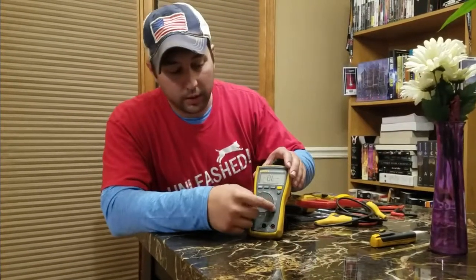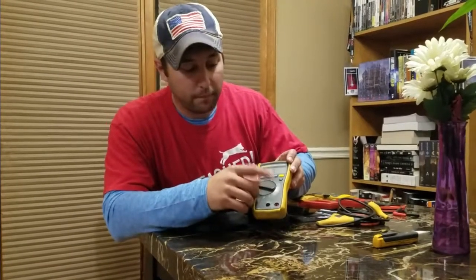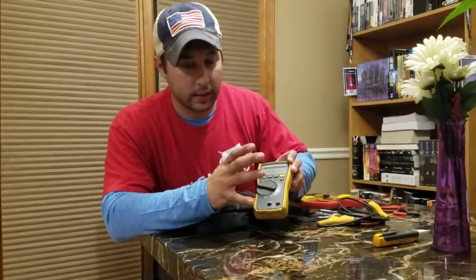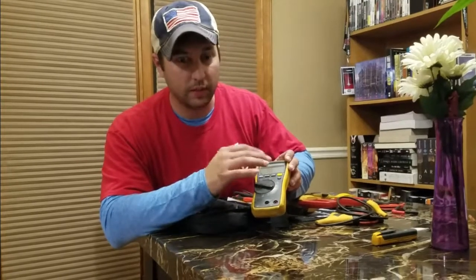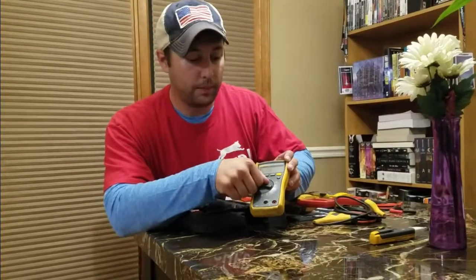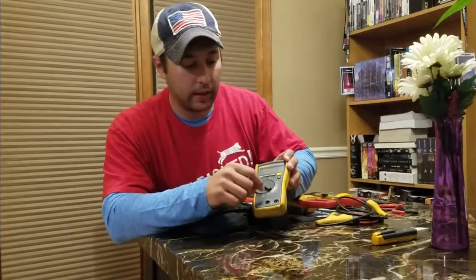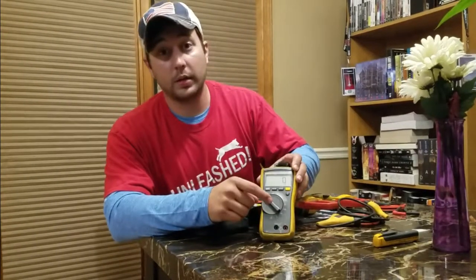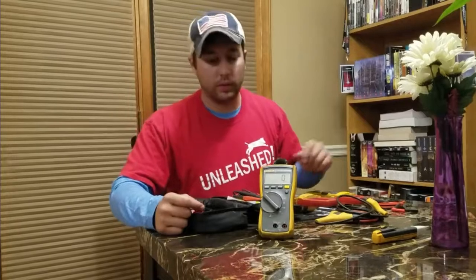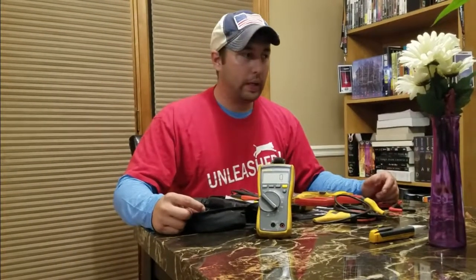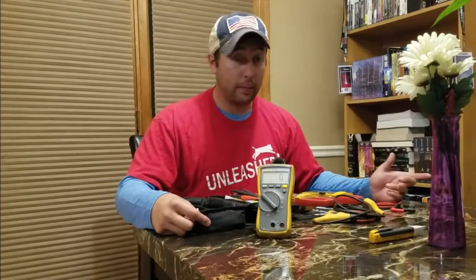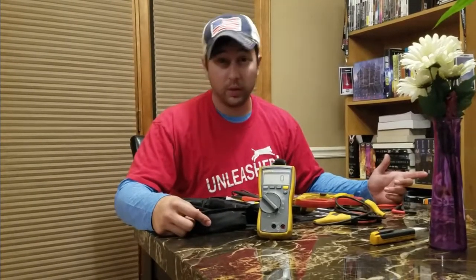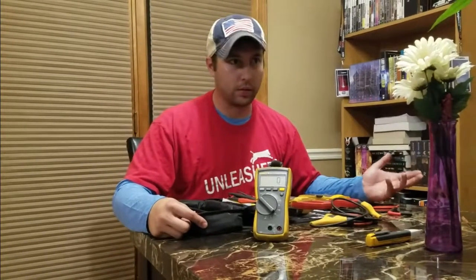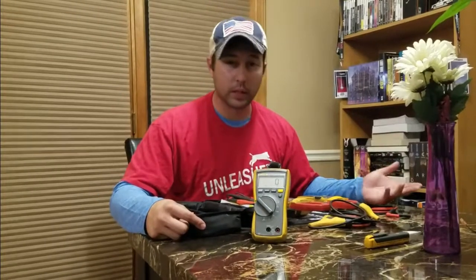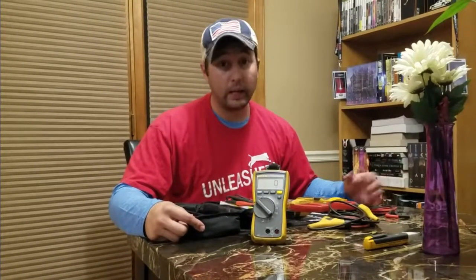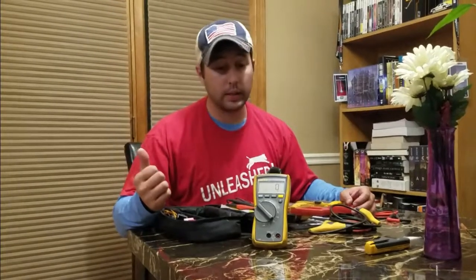The next feature down is continuity, which is the test light feature again, just without giving you the resistance value of the circuit. This one is actually a capacitor tester. You find those on different motors - in HVAC we see them a lot on fan motors. Residential and smaller single-phase equipment will have capacitors on compressors, blower motors, and things like that. That would probably be a handy feature for checking the air conditioning in the camper itself.